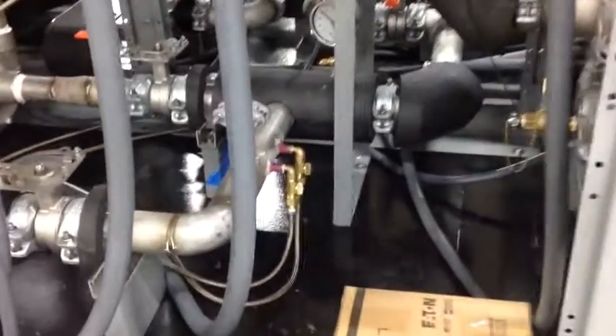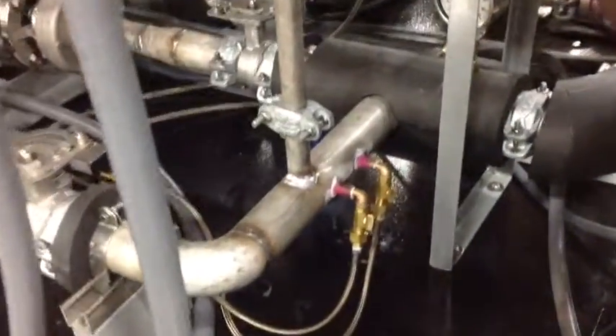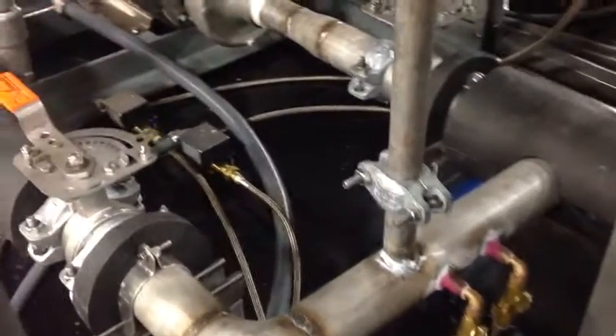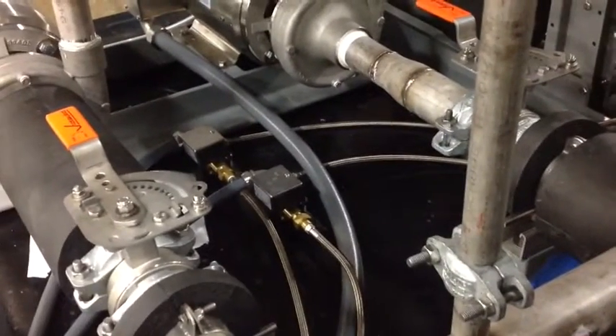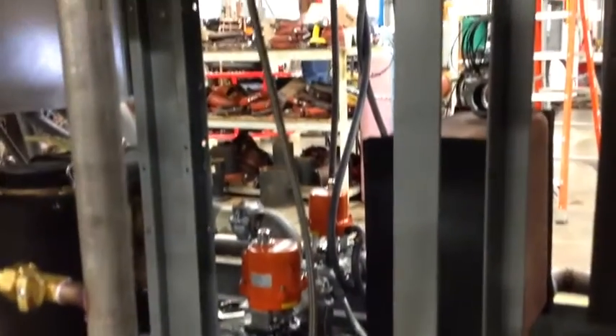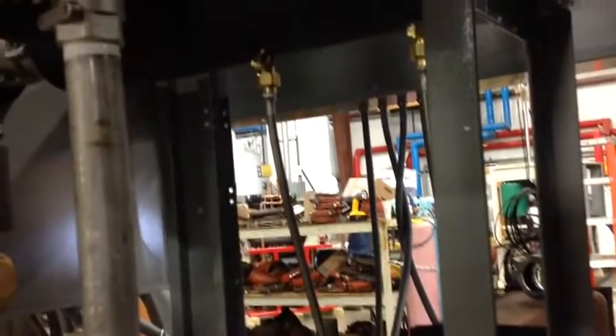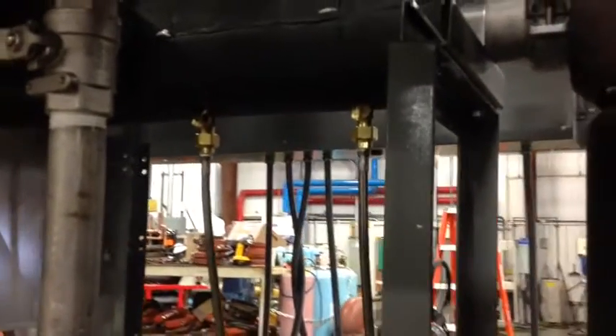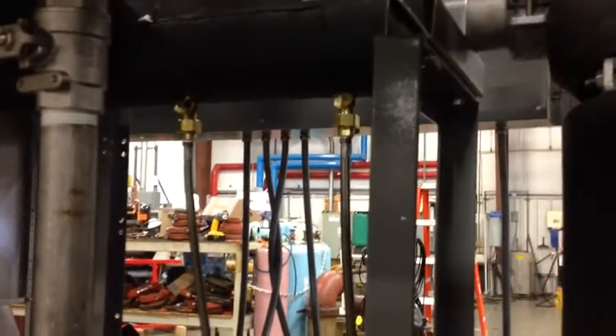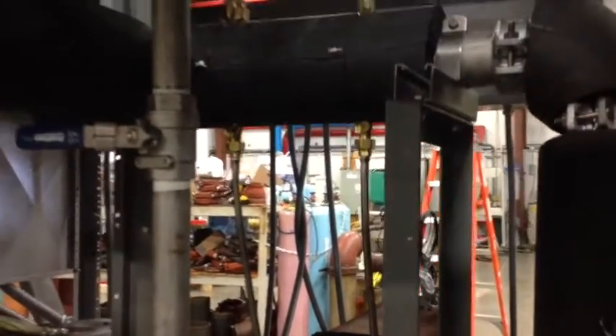The 2 gold valves there are both working toward the low side of the DP switches. You can see 2 of the DP switches there, and then the other hoses are going to the high side. Again, we have redundant differential pressure switches, and those are utilized to indicate pump failure and switch from the lead pump to the backup pump.